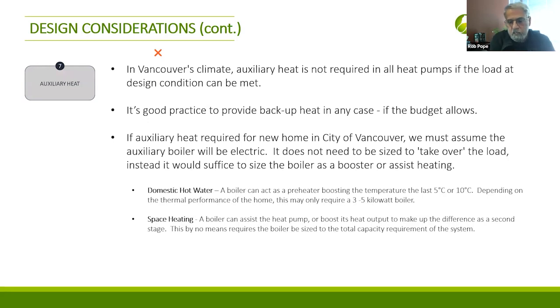The amount of auxiliary heat you need is really critical to understand. In most cases in BC, you need some auxiliary heat. You're going to have some, whether it's a boiler, a gas boiler for example, or electric strip doing the backup. It'll depend on a lot of things. It'll depend on how you met your metrics for step code compliance, for example. Right now, you can still do it. If you put a little extra effort into the insulation, windows, your building assemblies, and air tightness, those metrics can make it easier for you to put in a boiler.